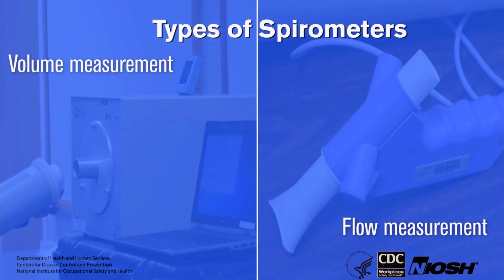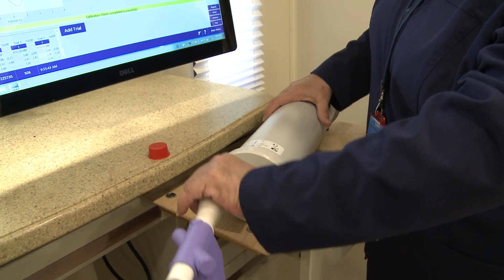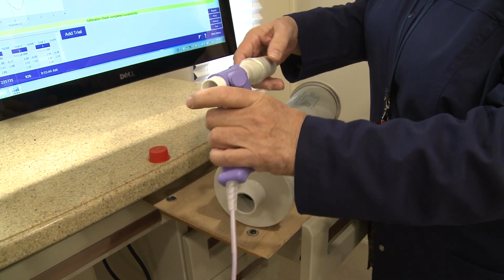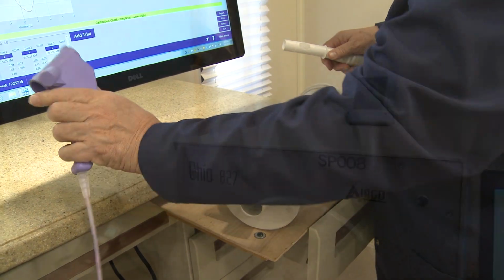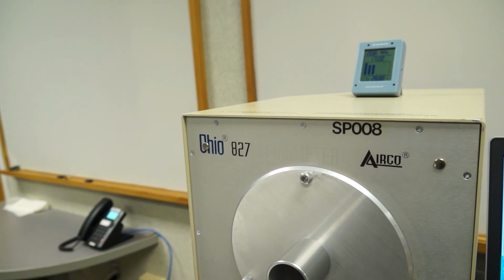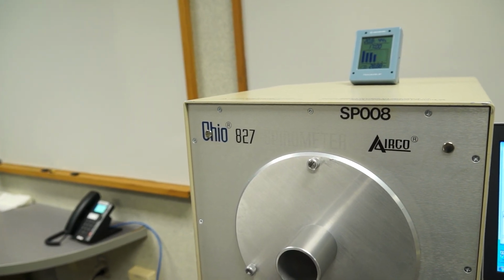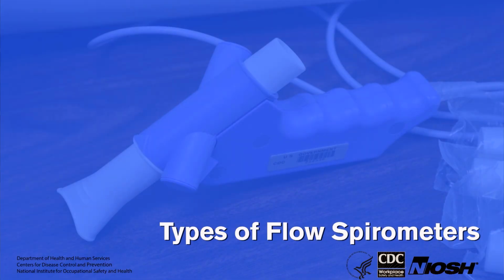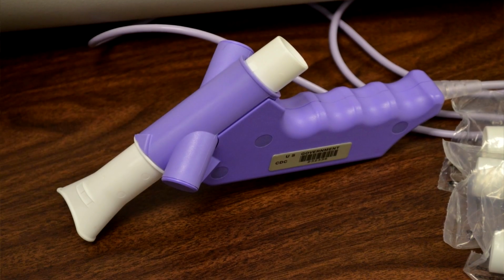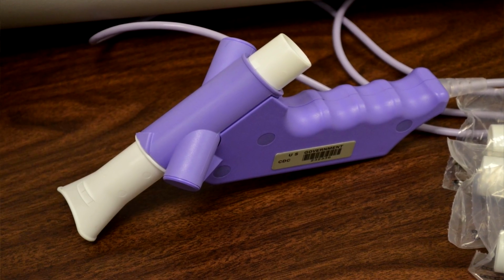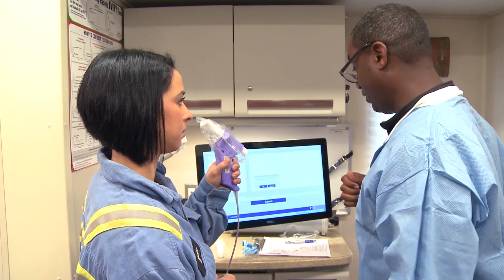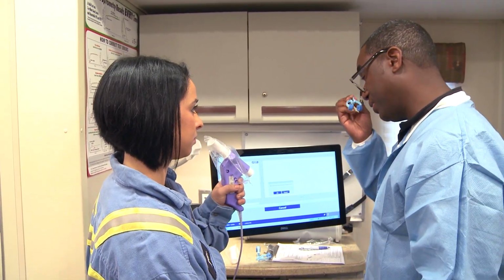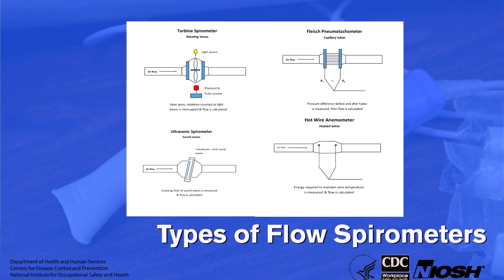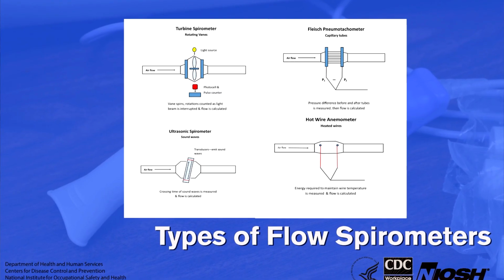There are 2 basic types of spirometers, flow and volume. The flow spirometer measures the speed at which air moves past a sensor. The other type of spirometer directly measures the volume of air. This is called a volume spirometer. Flow measuring spirometers directly measure airspeed through an open circuit and calculate volume. Most are smaller and more portable than volume spirometers. Flow spirometers use 4 basic measurement technologies to measure airspeed.